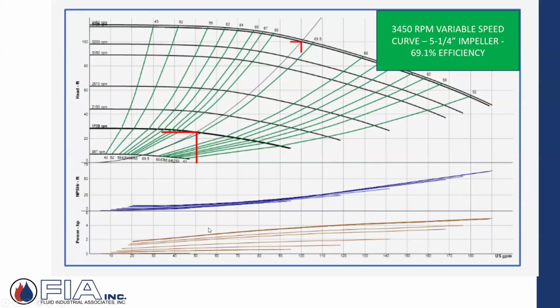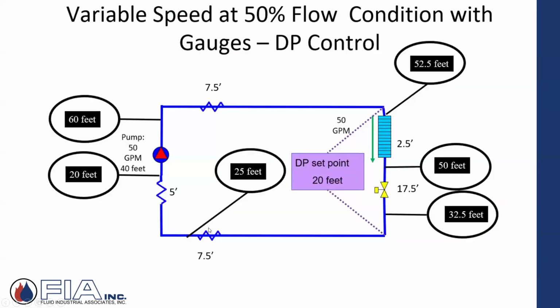I've reduced that flow by 50%, down to 50 gallons a minute. Here's my head, about 25 feet, just over 20, at that half flow, quarter head loss. And here it is, here's the curve. 1725 RPM, 3450 RPM. So same pump, change the speed. That's variable speed pumping. All you're doing is changing the speed.